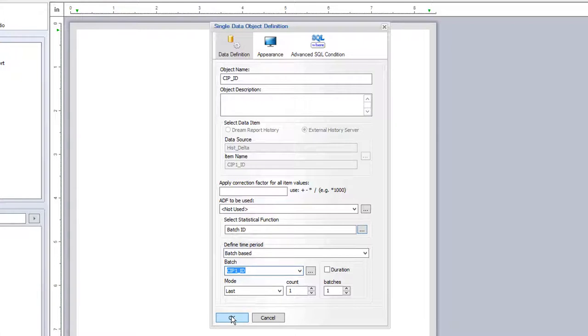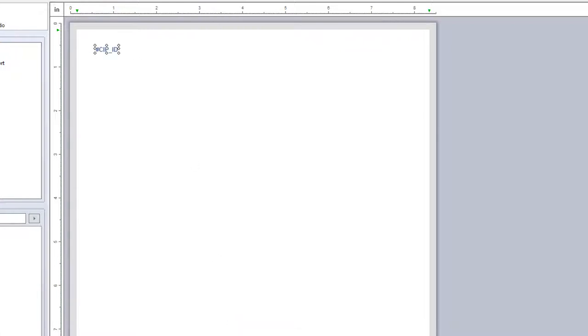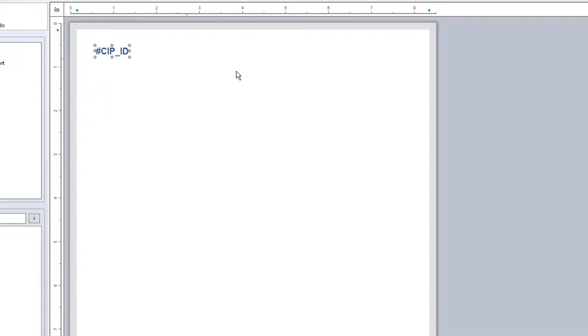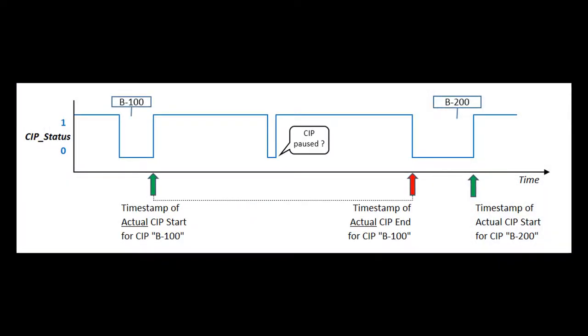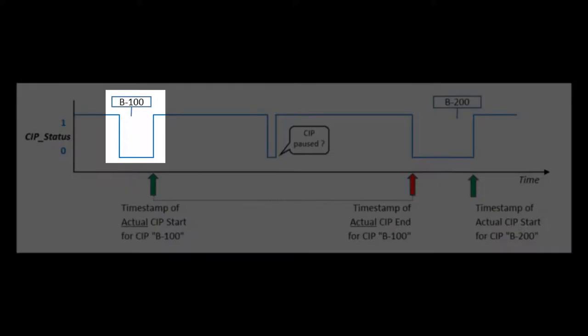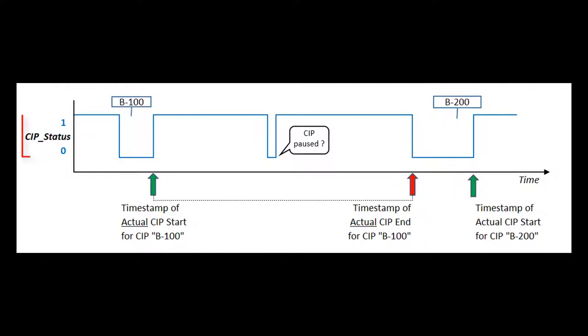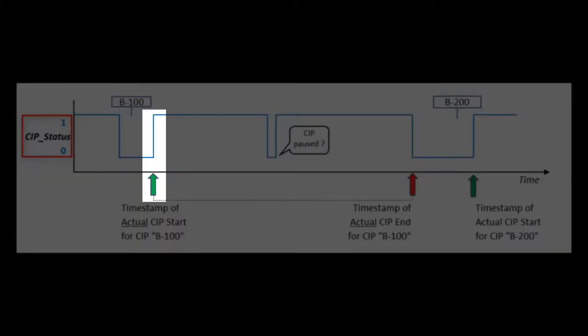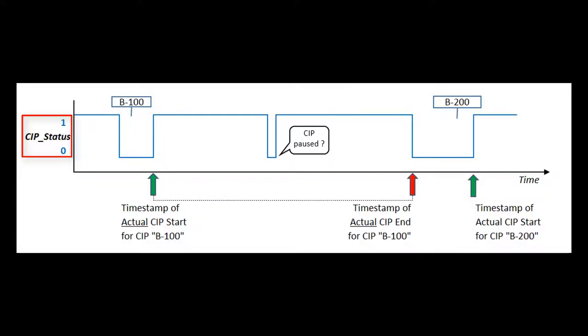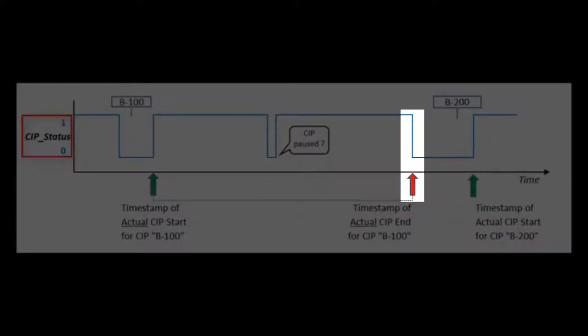By default, with batch definitions, DreamReport treats the change of a batch ID to be the end of the previous ID, so it's a continuous series of start and end times associated with each batch ID. In practice, however, there's typically a break or a pause between batches or CIP cycles. As such, we'll make use of a batch or a CIP status tag, that is set to 1 in the PLC or in the historian when the cycle starts, and then set or reset to 0 when it ends.